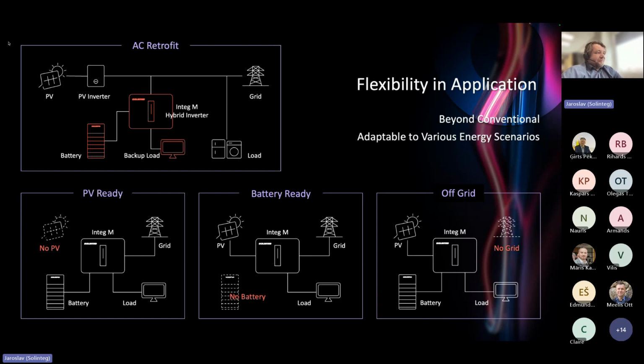The second picture is similar, also without PV modules, it's just PV ready. On the third picture, you can see this is battery ready. That means the hybrid inverter can work also without battery, and even in this case, the inverter can work asymmetrically. That means it can provide an unbalanced output. And the inverter can also work at 100% in off-grid mode without problems. That means without grid.